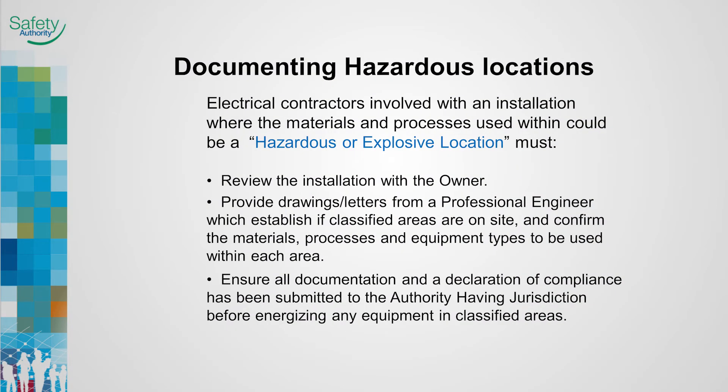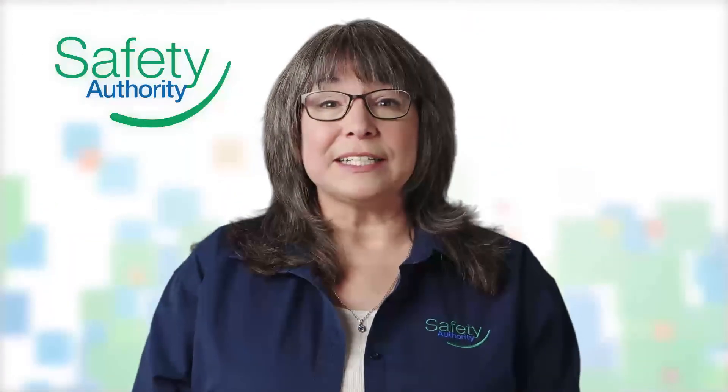Electrical contractors involved with an installation where the materials and processes used could create a hazardous or explosive location must review the installation with the owner, provide drawings and letters from the engineer which establish each classified area, and confirm the materials, processes, and equipment types to be used within. Ensure all documentation is complete and submit a declaration of compliance before energizing any equipment in classified areas. And remember, all dust is considered flammable unless it can be proven otherwise.